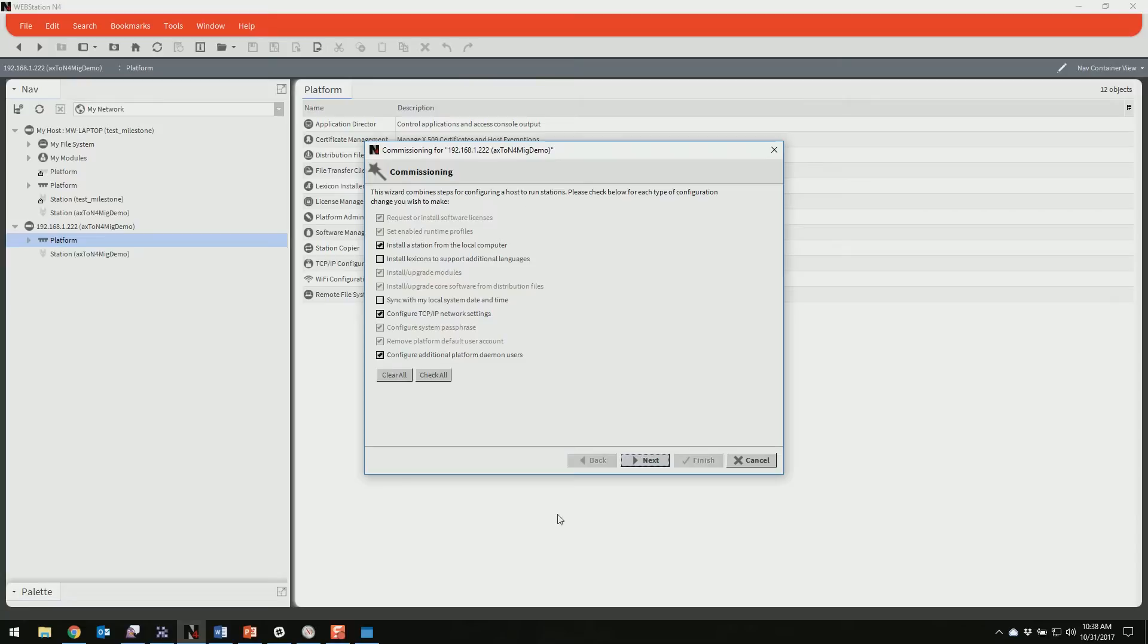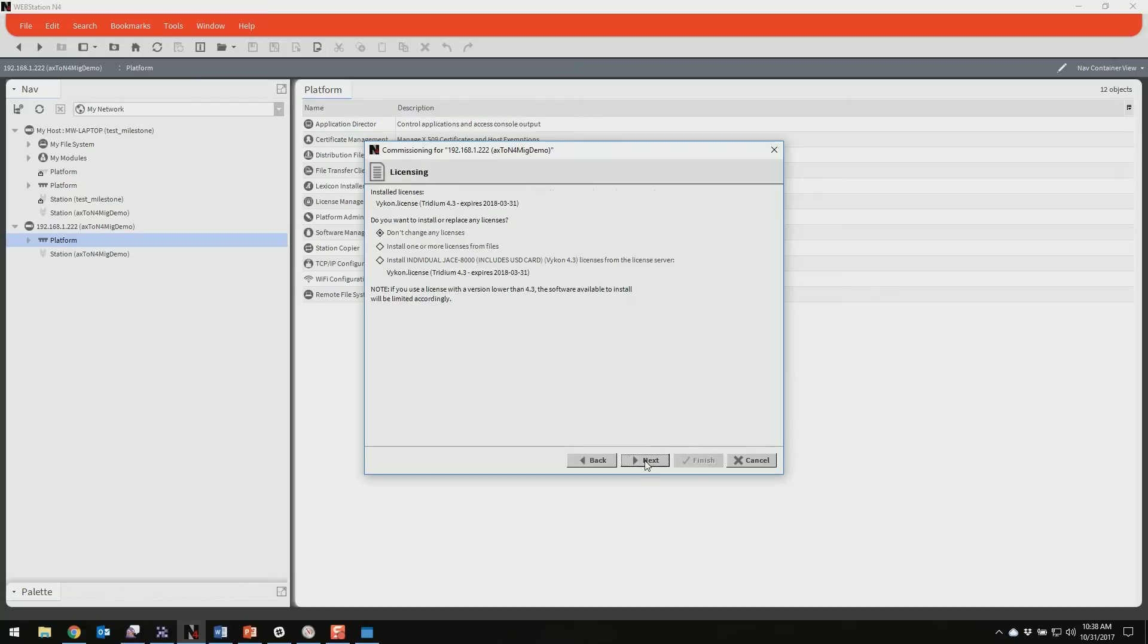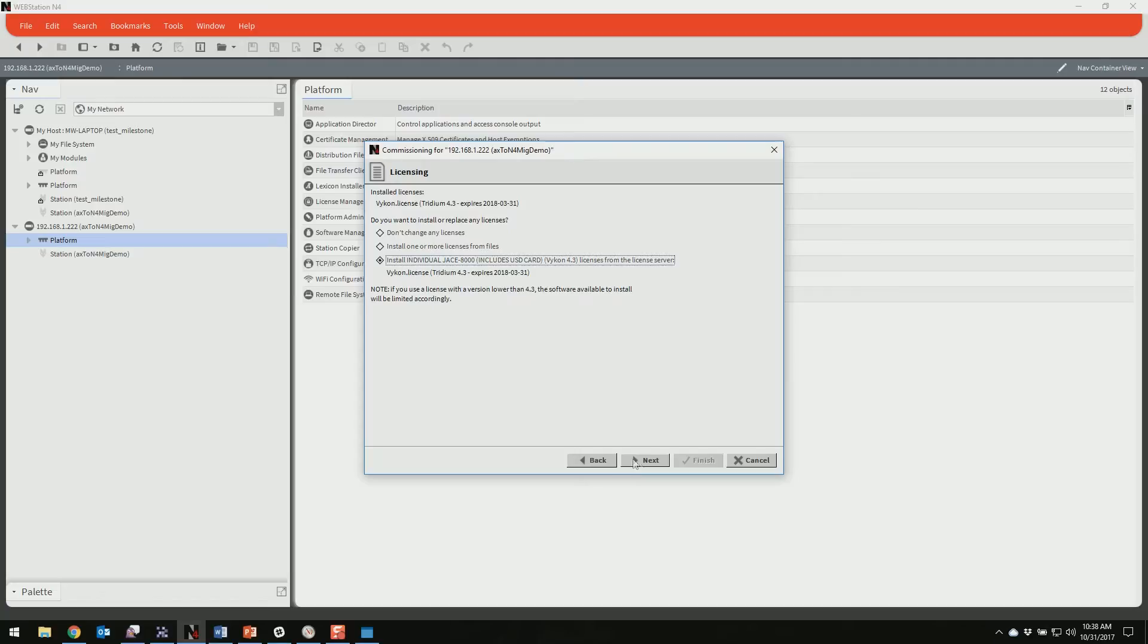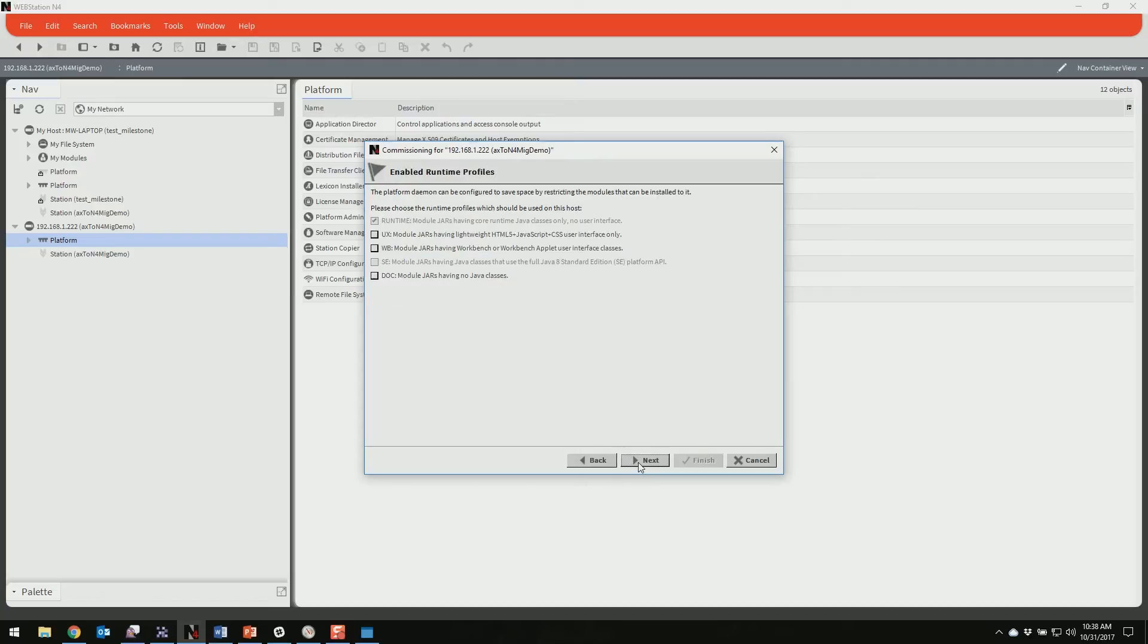You can leave all of the default stuff checked. It might also be a good idea to check the sync time. And if you're using the Jace in a different language, the lexicons, you'll need those as well. So you'll need to put a license in the Jace. I'll just tell it to put in a license. The license is already here in my case, but it's always good to pull the latest one in from the licensing server assuming you have internet access. The next step is going to ask you the runtime profiles.